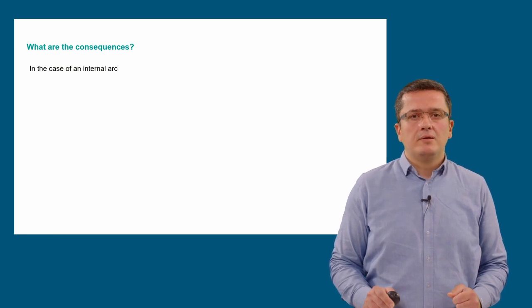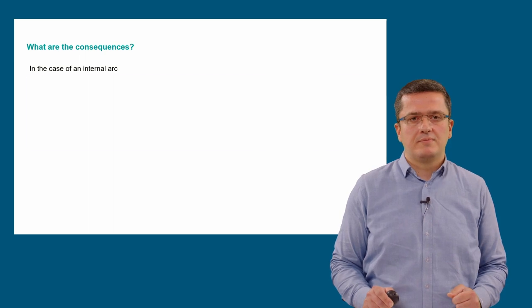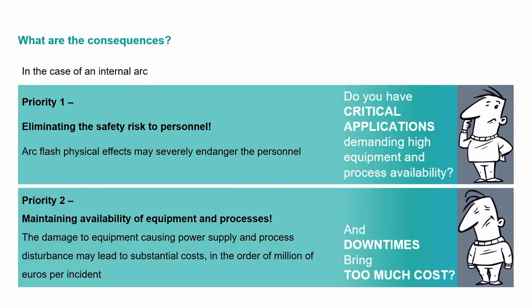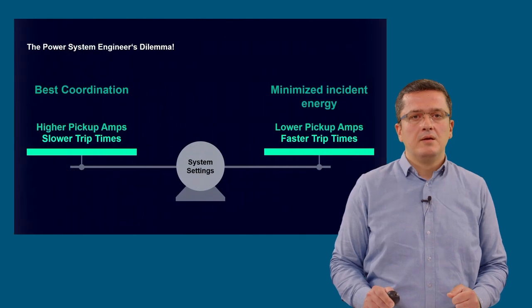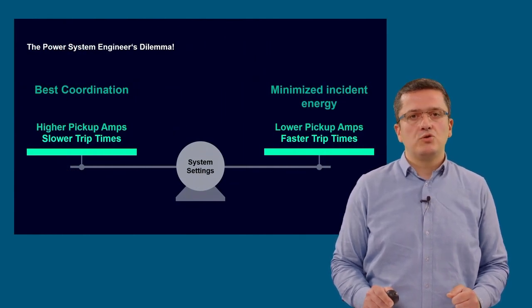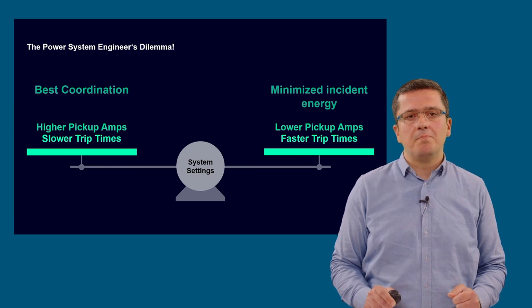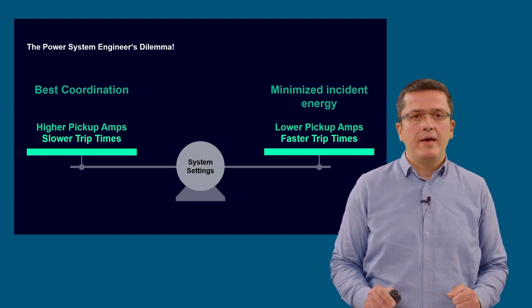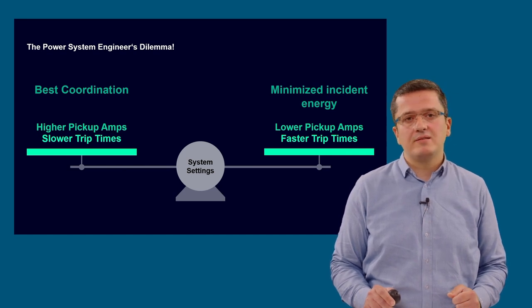In the case of an internal arc fault, priorities are clear to every one of us. First is to protect the personnel, as it may endanger their lives. Second is to keep the equipment and related processes available, as it may lead to substantial economic losses for the business. System engineers are in a dilemma. They should find the optimum balance between the best possible coordination settings to minimize the effects of unplanned shutdowns and the best possible safety of personnel. And each usually means sacrificing the other.